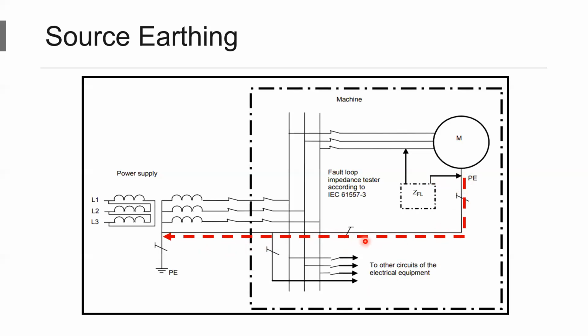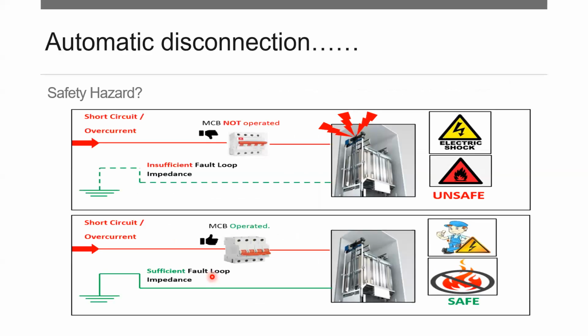Making localized earthings at the installation in the building premises is not going to help us take this fault current back to the source. So this is a major understanding gap as of today as far as the elevator industry is concerned. What is the safety hazard if the automatic disconnection does not happen? If the MCB does not trip because there is insufficient fault loop impedance, there could be chances of shock, or there could be a fire, and it could be unsafe for the elevator equipment as well as the users of the elevator. But if the MCB trips, the shock hazard is eliminated as well as the fire hazard. It means there is a sufficiently low fault impedance, which is sufficient to trip the MCBs during the fault conditions.